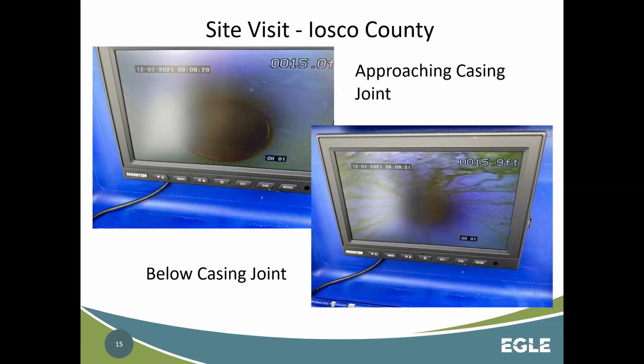So we decided we'd come out there with a downhole camera. We went down to the first joint. You can see on my mouse here, you can see all kinds of staining, iron staining at that first joint. And then as we passed it, you can see that shallow water, which had fairly poor water quality with iron, was basically running through that joint, which wasn't sealed with the glue, and running down into the well. So all that shallow groundwater was getting into the well, causing bacteriological problems.